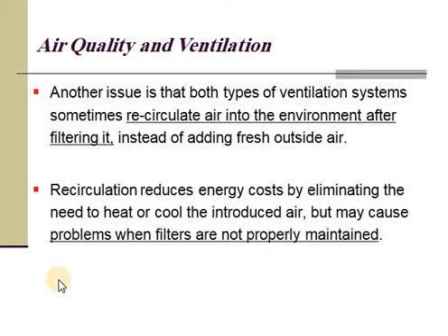Now, why do they do that? They do that to reduce the cost of energy, because if they recirculate the already cooled air back into the work environment, they will be reducing the cost of getting fresh air. This fresh air from outside might be very hot. They will have to cool it down first by air conditioning, then introduce it to the work environment. So they find it cheaper to recirculate the diluted or the filtered air.